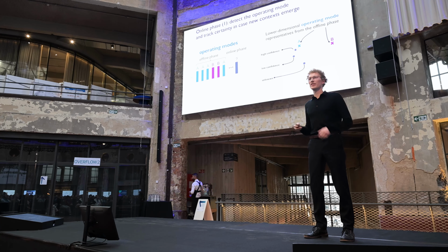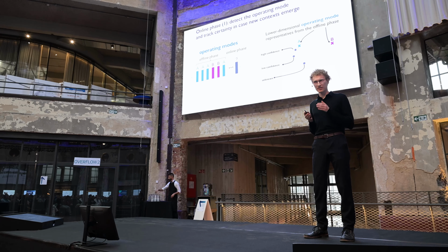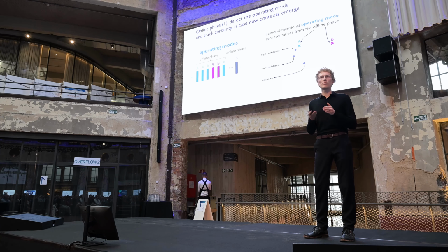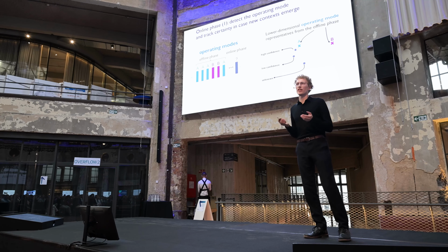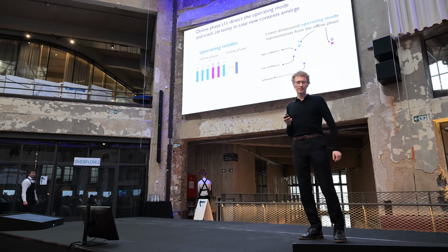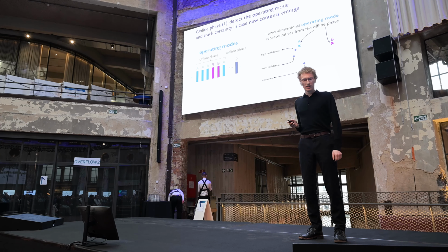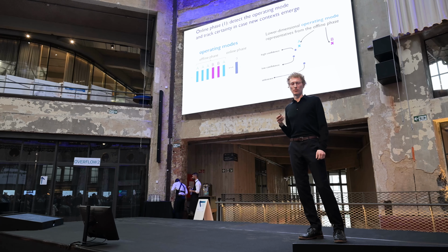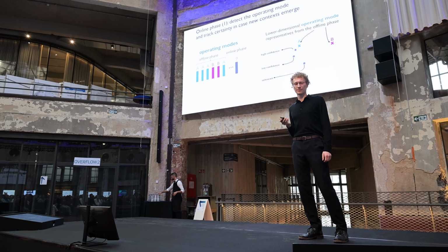Now, in the online phase, it comes to the anomaly detection. But first, we need to make sure that we predict the operating context correctly. And more importantly, it could be that a new operating context emerges online. For instance, a different combination of rotational speeds and flow, and we should make sure that we detect that. This is done by comparing the operating mode representatives that you can see on the right with the actual operating point of the asset at the moment. If they are very different, then we will assign an unknown operating mode.